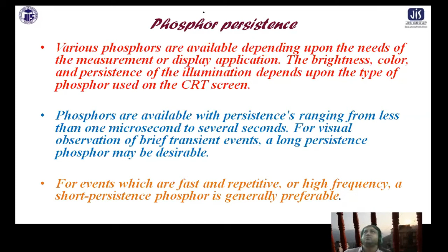Now various phosphors are available depending upon the color. How do you produce it? By impinging electrons on the phosphor screen. So various types of phosphors are available depending upon the needs of the measurement or display application. The brightness, color and persistence of the illumination depend on the type of phosphor used on the CRT screen. Phosphors are available with persistence ranging from less than 1 microsecond to several seconds. Persistence means how much time the phosphor is actually keeping the light on.